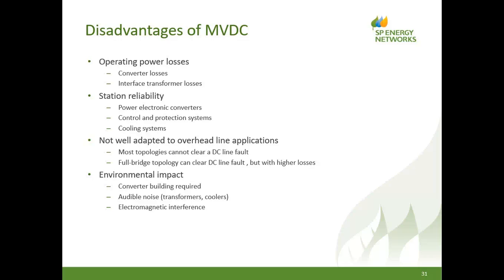One issue that we are aware of is that the topology we're using is not well adapted to overhead line application. So if we have a fault on the short length of 27 kV, as it will become, DC overhead line, the topology itself, the power electronic itself, cannot clear the fault. So we'll have to open the AC circuit breakers, as we would do now with an AC system. Many HVDC stations can deal with such DC faults, but not the topology we're using here, and indeed not the topology that is widely used for HVDC applications.